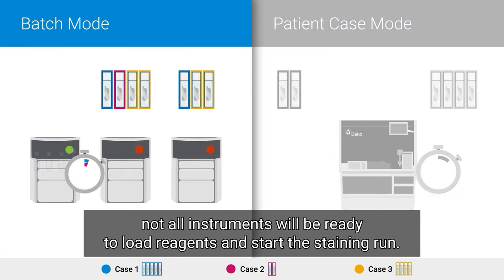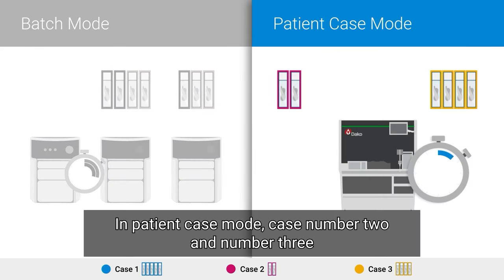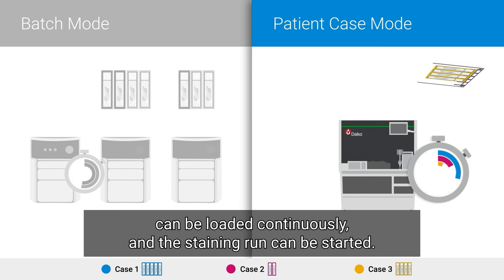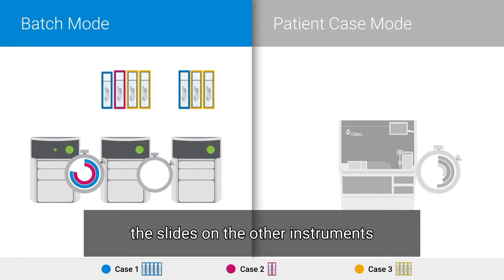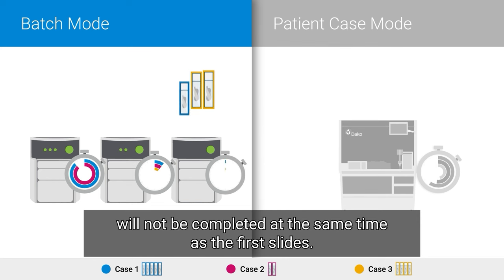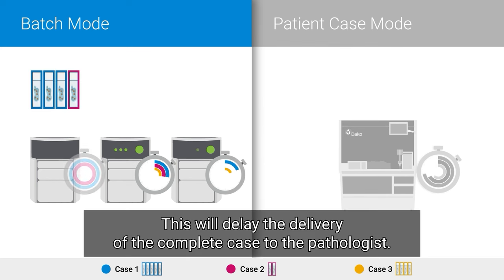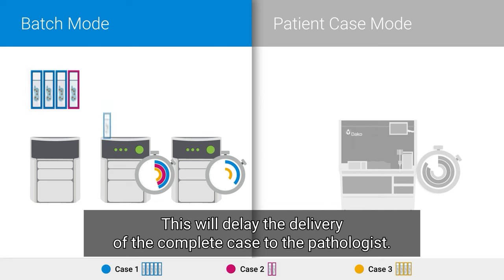In batch mode, not all instruments will be ready to load reagents and start the staining run. In patient case mode, case number 2 and number 3 can be loaded continuously and the staining run can be started. With the delayed start, the slides on the other instruments will not be completed at the same time as the first slides, which will delay the delivery of the complete case to the pathologist.